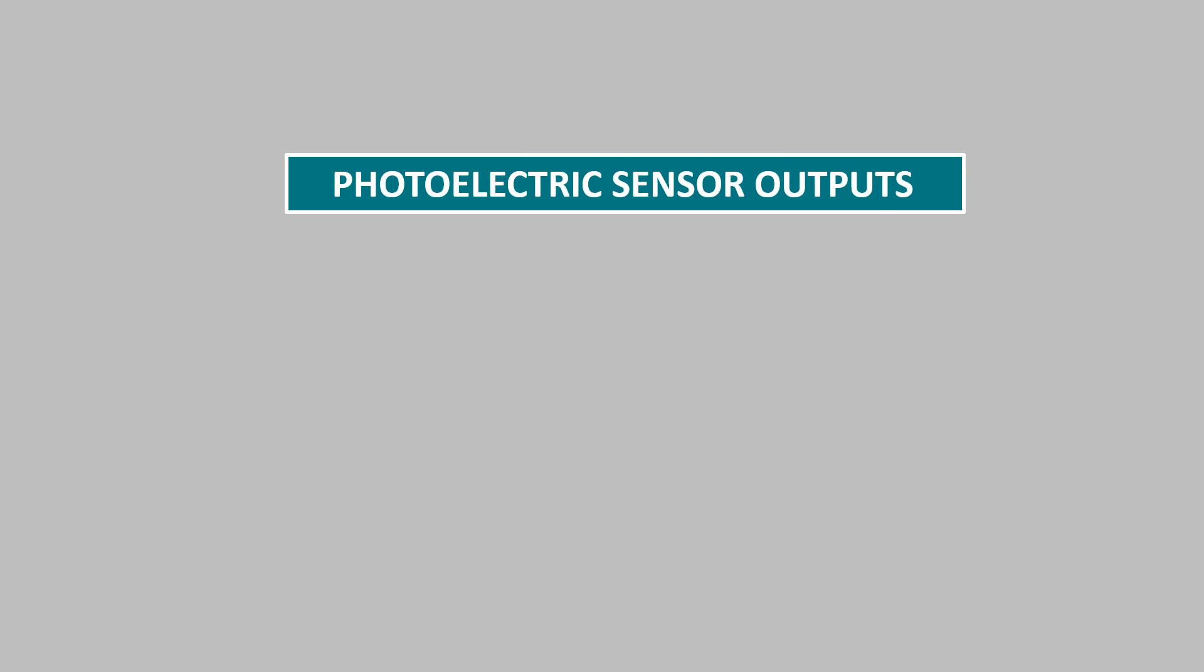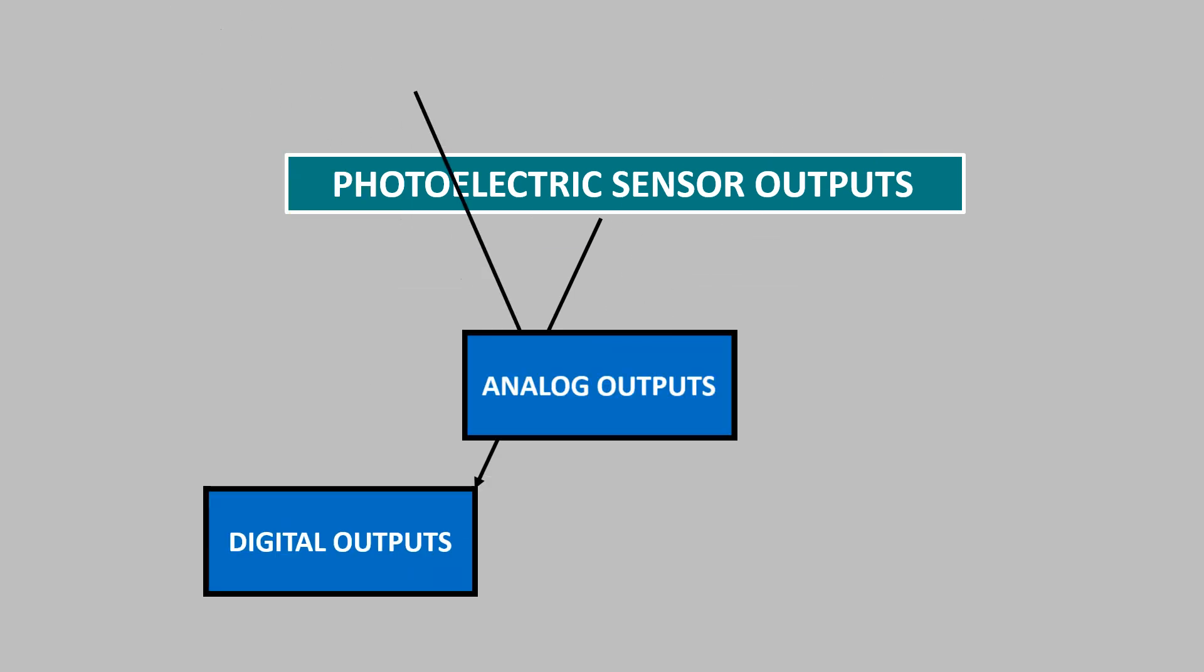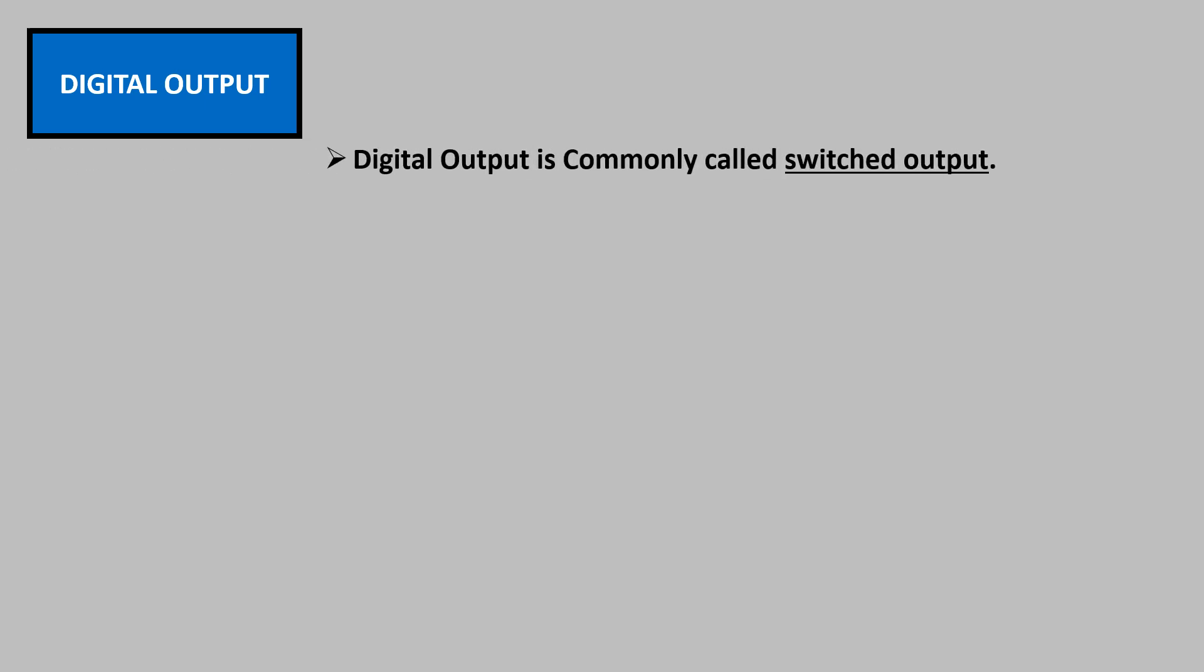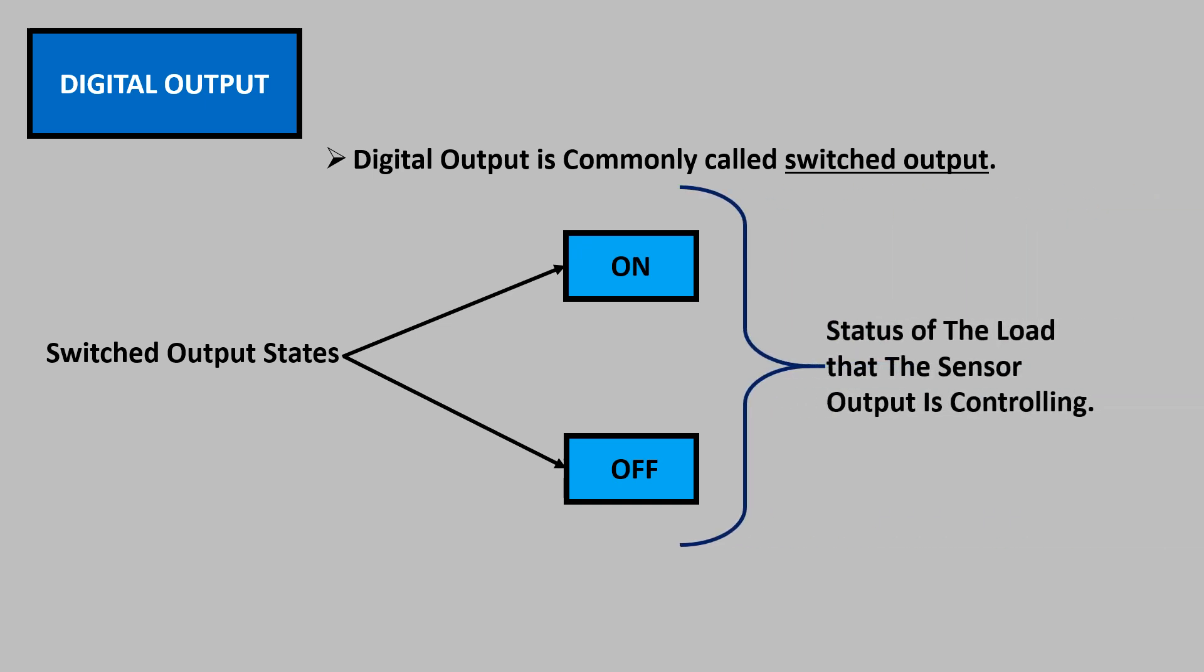Now let's discuss photoelectric sensor outputs. The output of photoelectric sensors are of two types: digital or analog outputs. Digital output is commonly called a switched output. A switched output has only two states, on and off. This on and off states commonly refer to the status of the load that the sensor output is controlling. The load might be an audible alarm, an indicator light, a switching relay, or a PLC.